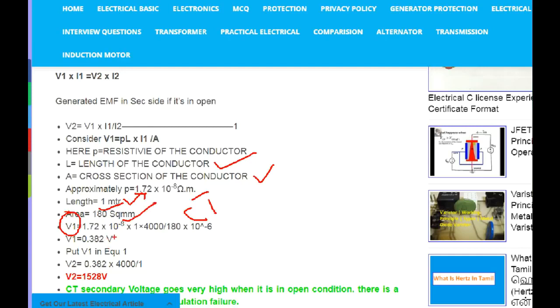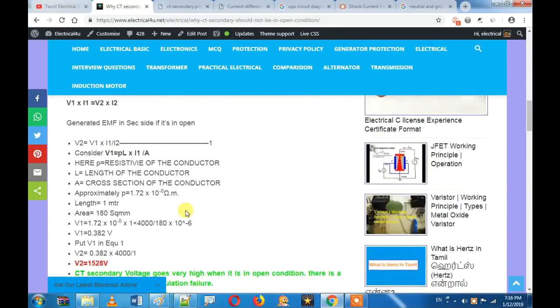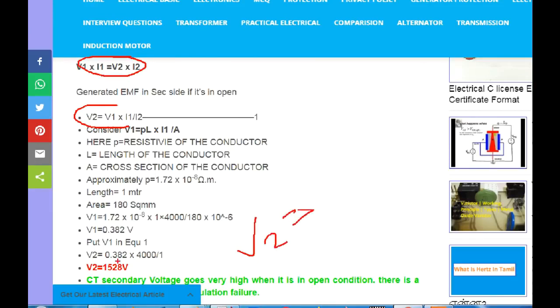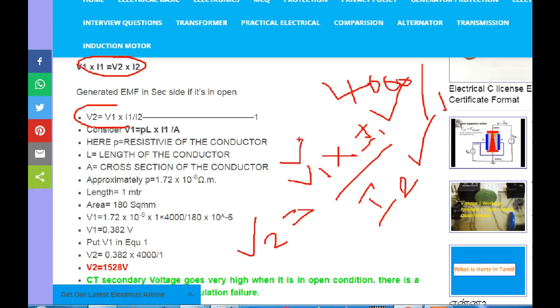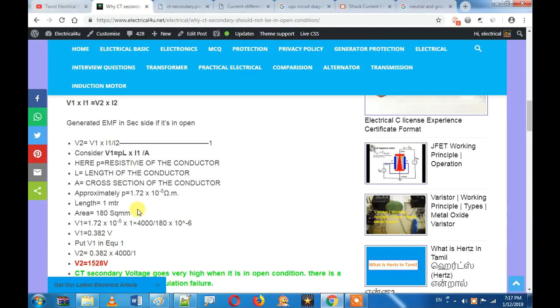We can substitute V1. The V1 output drop is 0.382 — that is the voltage drop. The CT drop is 0.382. Substituting into the formula: V2 equals V1 into I1 divided by I2. We already know I1 and I2 are 4000/1, so V2 works out to 1.25 kV for a 4000/1 CT.